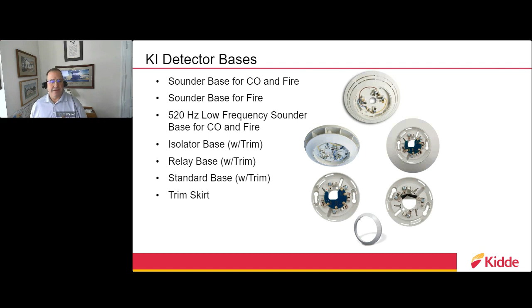To kind of expand on something there regarding the 520 hertz low frequency device or base. So if you didn't know, the 2021 International Building and International Fire Code, which were released basically last year, have now changed some code sections for the group R1 and R2, which are your sleeping occupancies for hotels, dormitories, and as such. The requirement that is changed is what they classify in the smoke alarm section. Smoke alarm in our world of the fire and life safety industry represents your 120 volt AC powered device with a battery. And in those code sections, they've actually stated that we need to have what's called a 520 hertz signal produced from the detector when it activates.